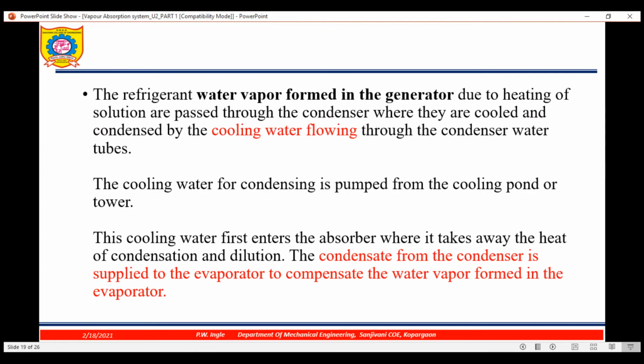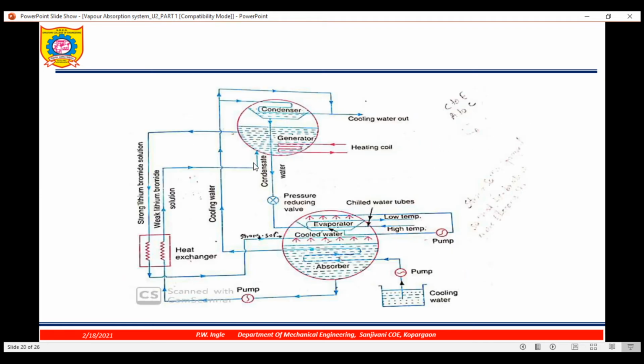Now next, the refrigerant water vapor formed in the generator due to heating of the solution is passed through the condenser, where it is cooled and condensed by cooling water flowing through the condenser water tube. Now here you see, we are getting what? Water vapor as refrigerant, because it will get separated out from the LiBr solution. So that will be condensed by cooling water.